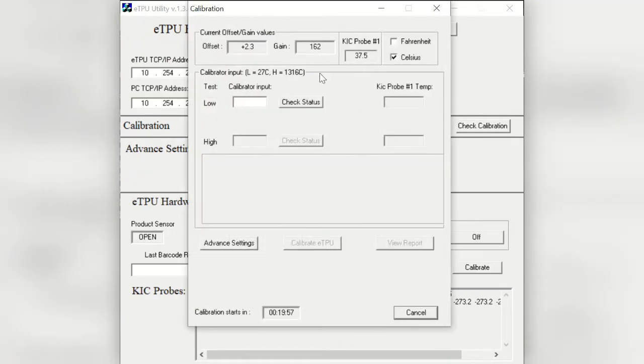Now click on Check Calibration. A new window should pop up. Notice in the lower left corner, our timer countdown has started. We wait 20 minutes to allow the cold joint references of both units to stabilize to the same temperature. In the upper part of the window, you see the current offset value, gain, and the current live KIC probe TC readings. In the checkbox, you can choose between Celsius or Fahrenheit for units of measure.